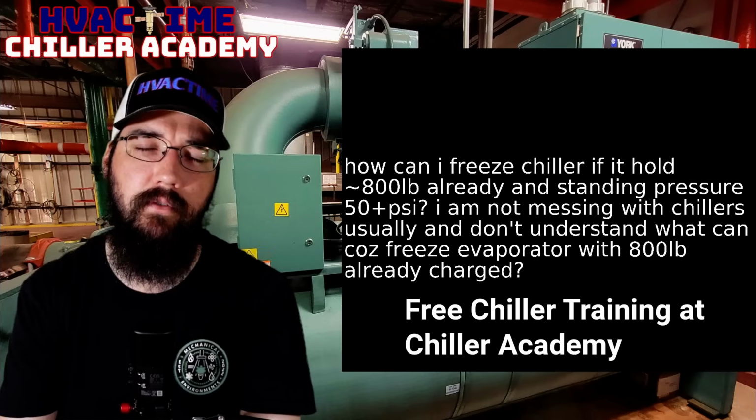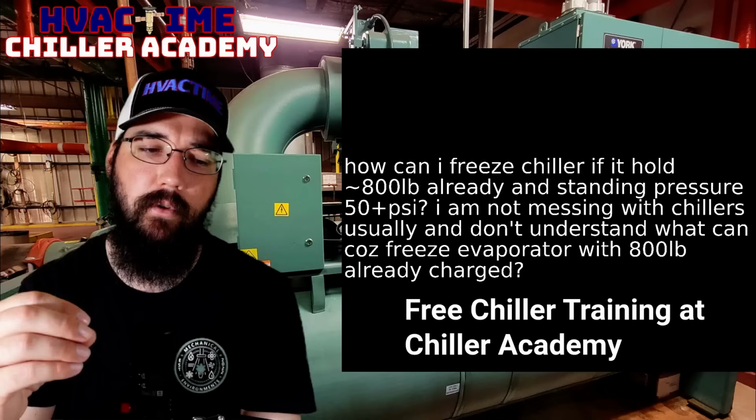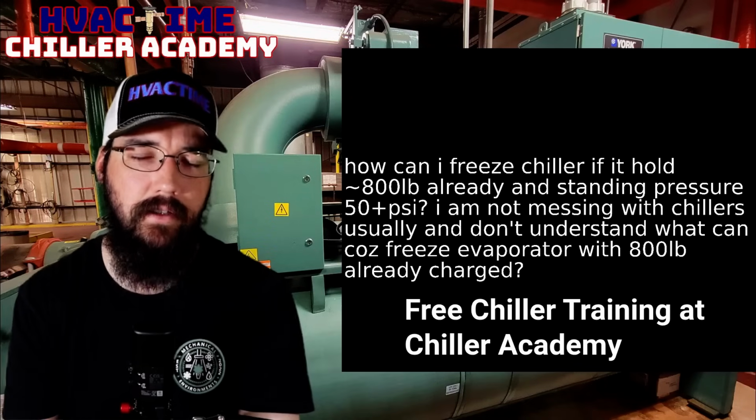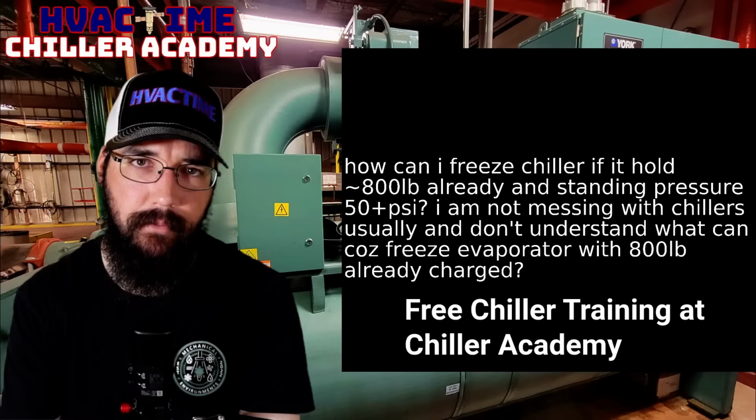If you're flowing water, there are still ways of mitigating that risk and that problem. Flowing water would be one of them. And either way you go with it, it is still recommended to flow water, whether you pre-charge vapor or not. But the key there is the saturation temperature.